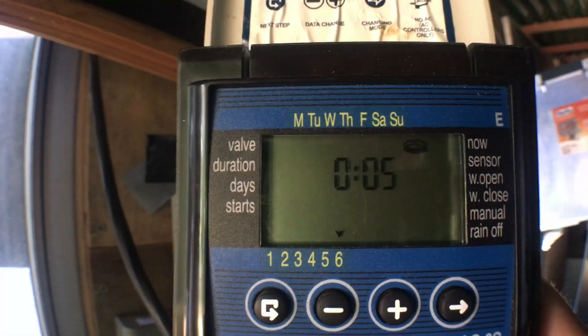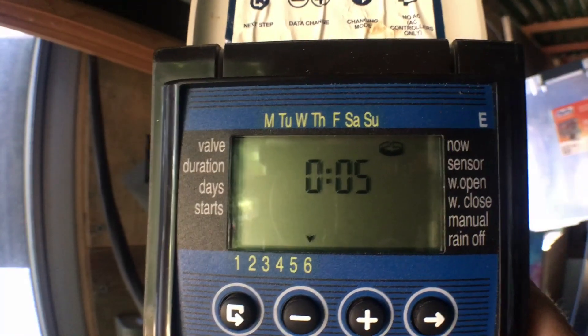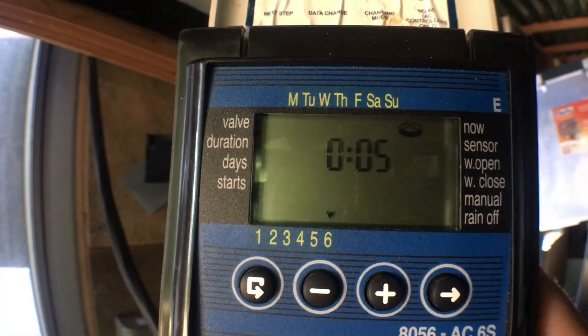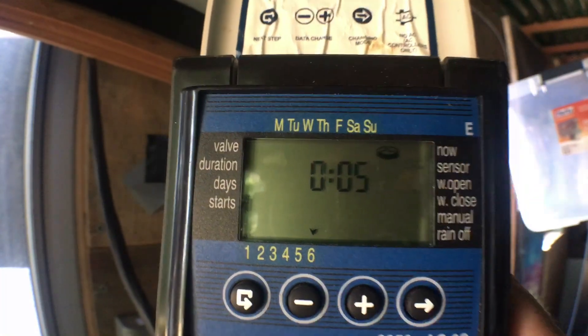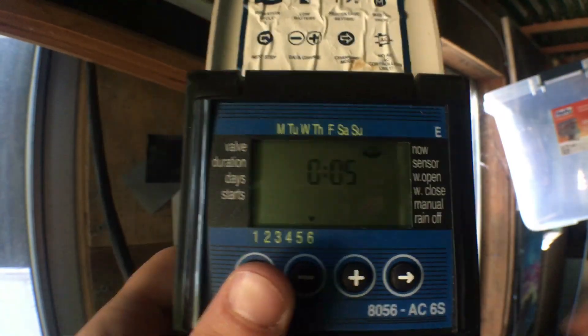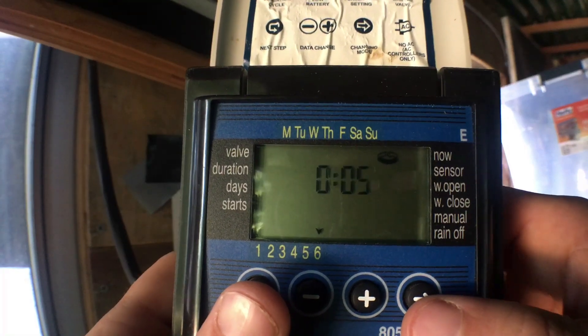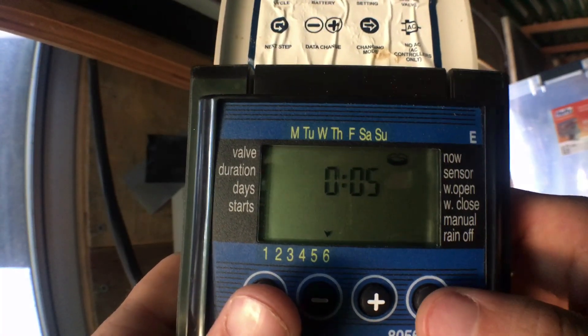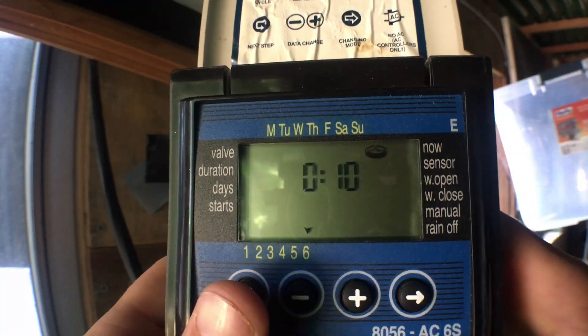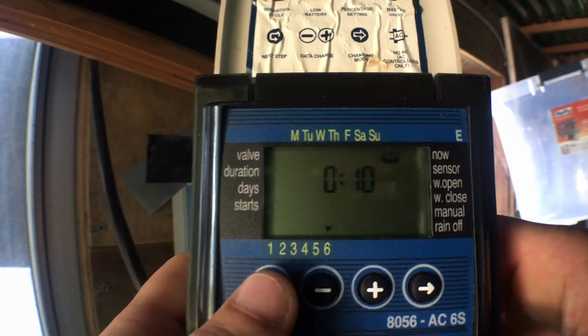This is a misting bed set on cyclic irrigation, which means every single day it works during a preset time window. It just goes — and this setting means that every five minutes, this valve will open for 40 seconds. I want to change this to ten minutes, so I'll go up. Five minutes is the smallest interval you can get; ten is the next up. I'm happy with that, so I'll hit select.